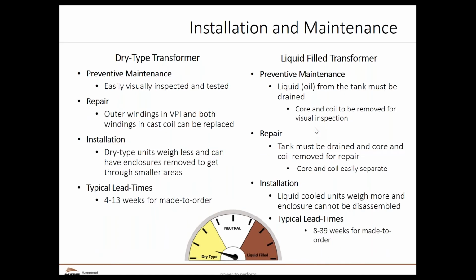Maintenance is also very different. Obviously, with the dry type, I can de-energize the transformer, and I can physically go in and inspect the coils. I can test them easily. If I need to repair something in a coil, whether it's a loose fitting or something like that, I generally can get to it fairly easily. I don't have to drain any oil out, and I can deal with it.